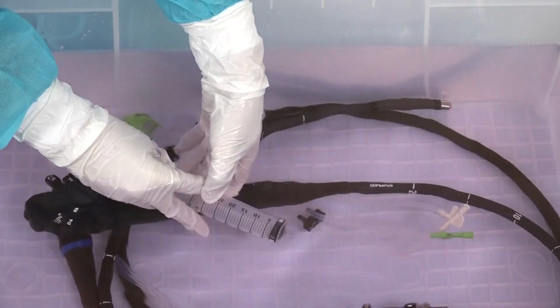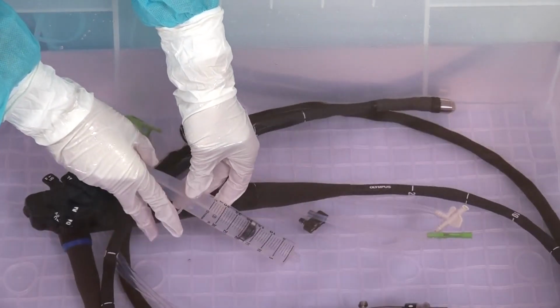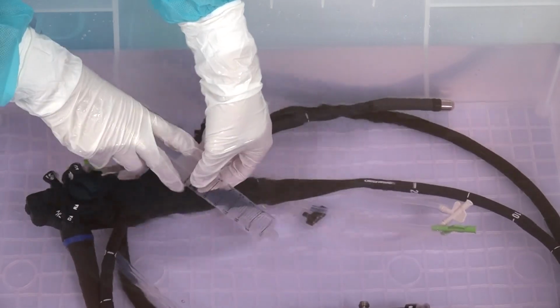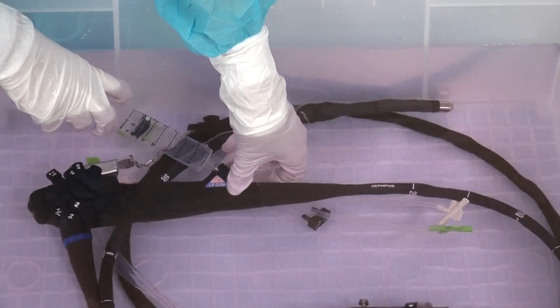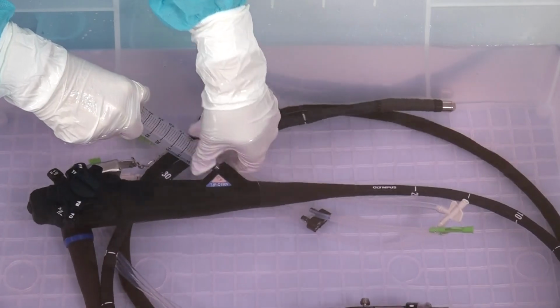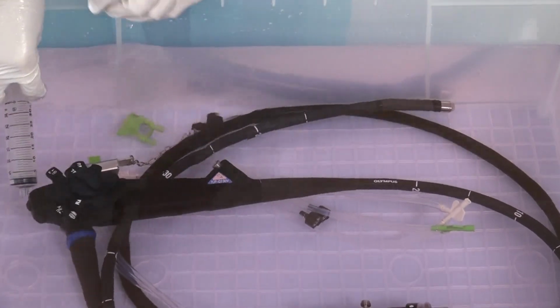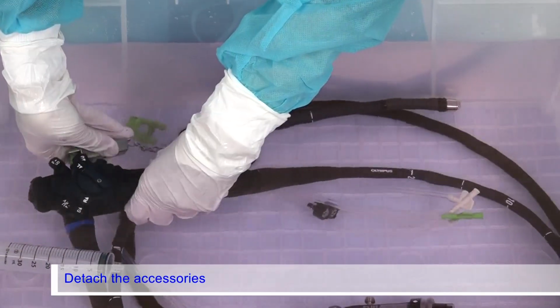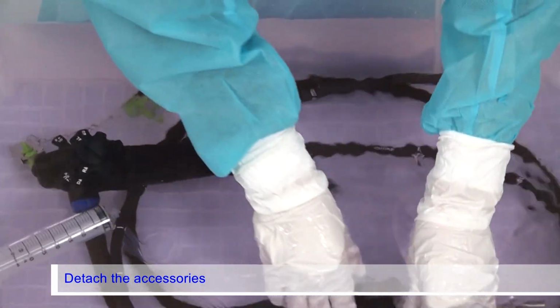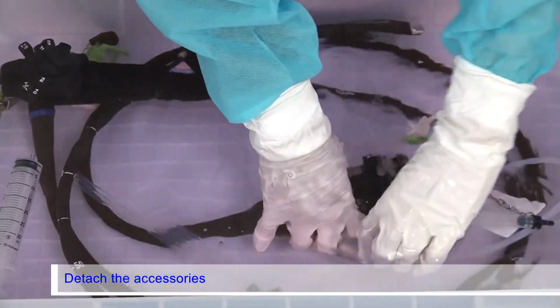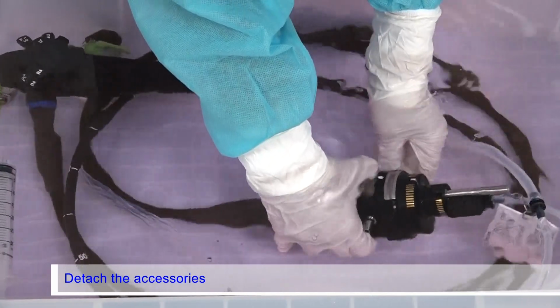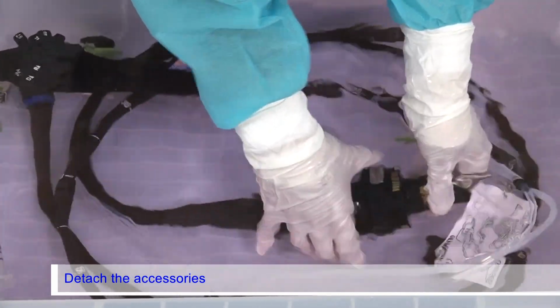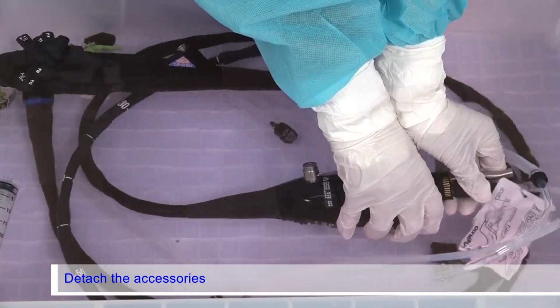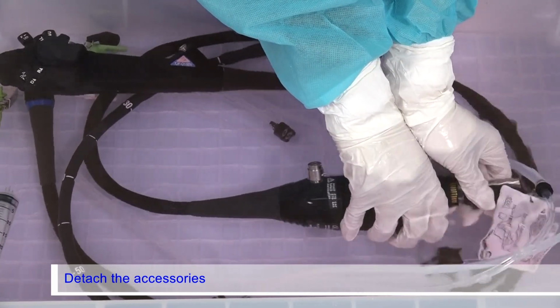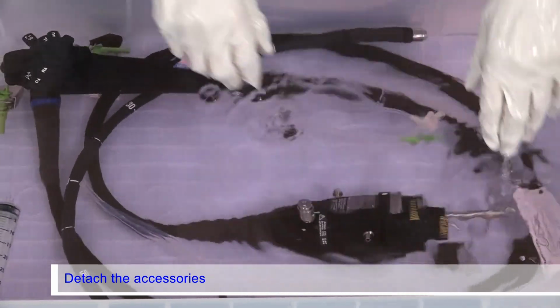Confirm that no air bubbles exit the distal end during the last flush. If air bubbles still exit, flush the channel with the disinfectant solution until no air bubbles exit. While immersing the endoscope and all accessories completely, detach the channel plug and the injection tube. Confirm that the endoscope and all accessories are completely immersed in the disinfectant solution.